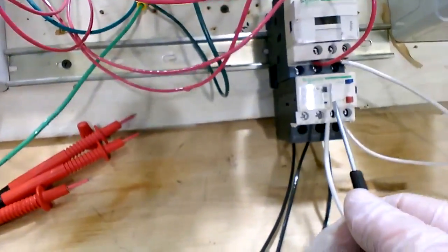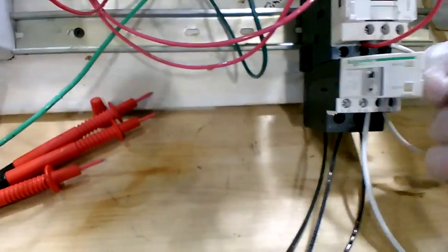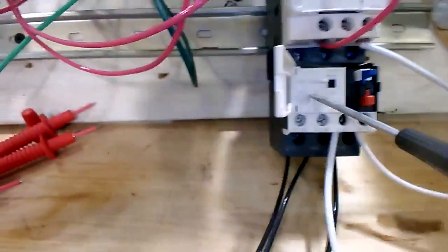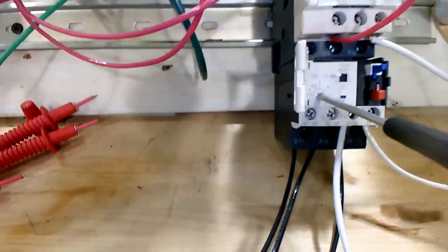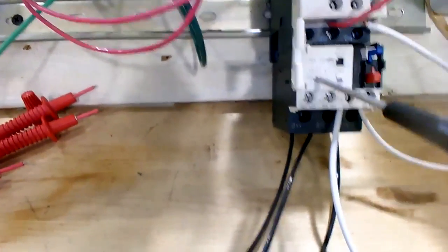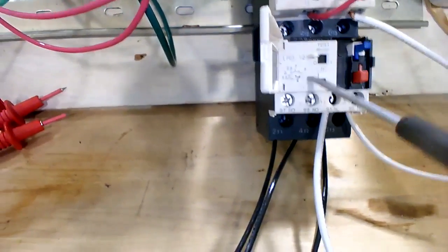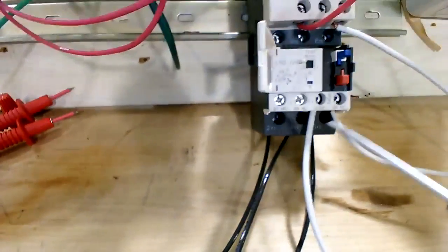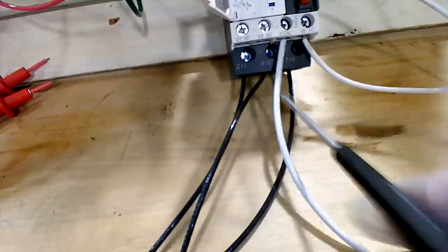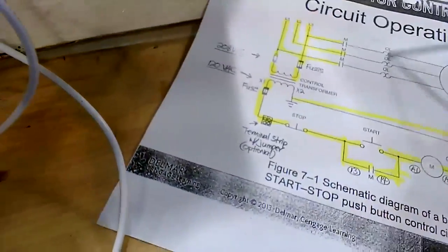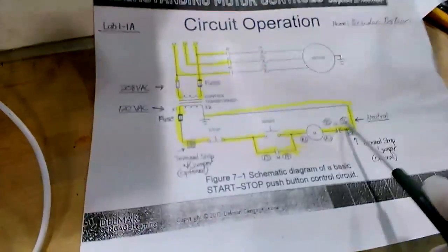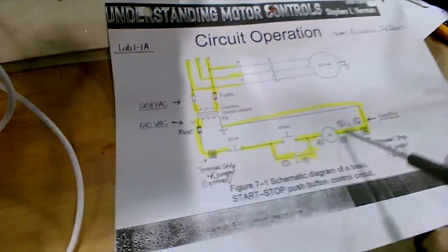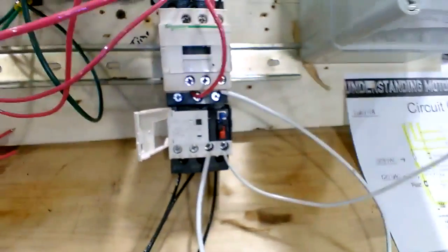And if you have issues with this overload relay tripping, it will trip if you draw too many amps. Inside of here, there's a dial. That dial determines how many amps it trips at. This one can be set from 5.5 amps to 8 amps, and that's the range of this one. They make them in different ranges. If you exceed the setting, it's going to trip out. It causes that normally closed contact to pop open. If they get too hot in there with too much current, it causes that to pop open, and it cuts the neutral side of the coil, and the whole thing shuts down.